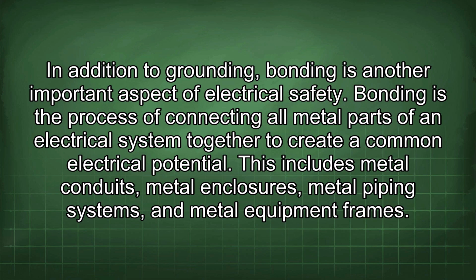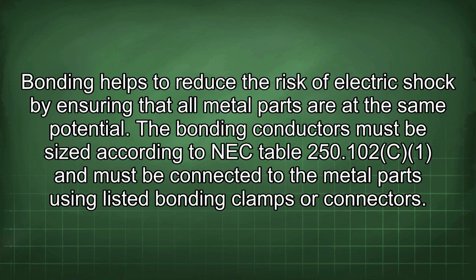In addition to grounding, bonding is another important aspect of electrical safety. Bonding is the process of connecting all metal parts of an electrical system together to create a common electrical potential. This includes metal conduits, metal enclosures, metal piping systems, and metal equipment frames. Bonding helps to reduce the risk of electric shock by ensuring that all metal parts are at the same potential. The bonding conductors must be sized according to NEC Table 250.102 and must be connected to the metal parts using listed bonding clamps or connectors.